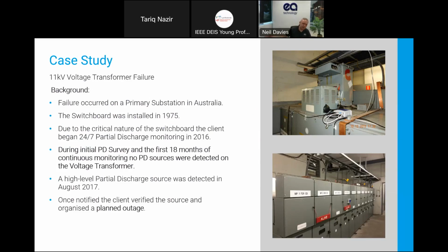Now, during the first 18 months of monitoring, no partial discharge sources were detected on this VT. So if you think about that, if I was testing not on an annual basis, but on a monthly basis, going in there testing, am I detecting nothing? I'm getting nothing for 17, 18 months, and then all of a sudden I've got something. So a high-level source kicked up in August 2017. The client was notified and an outage was planned.